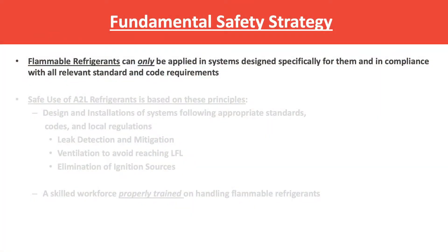The adoption of A2Ls is really fundamentally based on safety — being able to install, service, and design systems so they can be used safely for their environmental properties, while mitigating any flammability hazards. First and foremost, these flammable refrigerants are only going to be used in new equipment that was designed to mitigate the flammability — equipment designed, installed, and serviced for safe use. We're not going to see A2Ls put into traditional systems already in the field. We're not going to retrofit a 410A air conditioner with an A2L refrigerant.